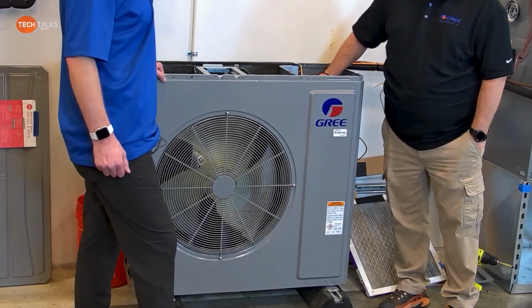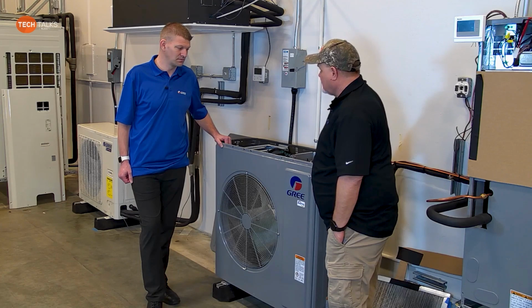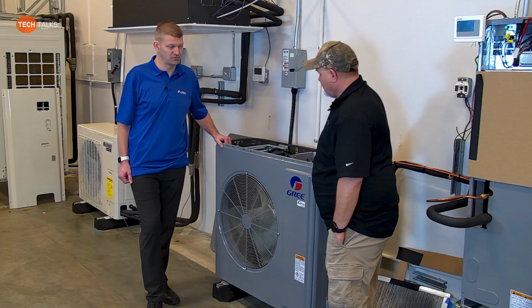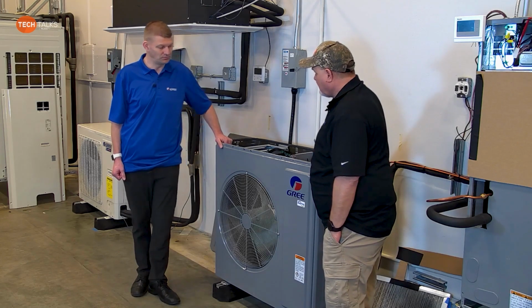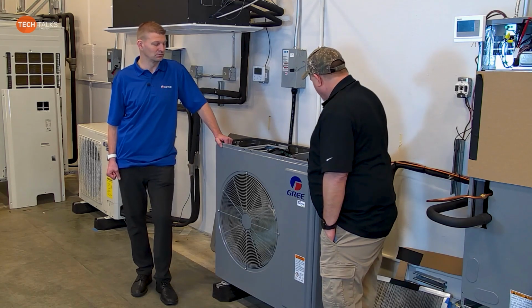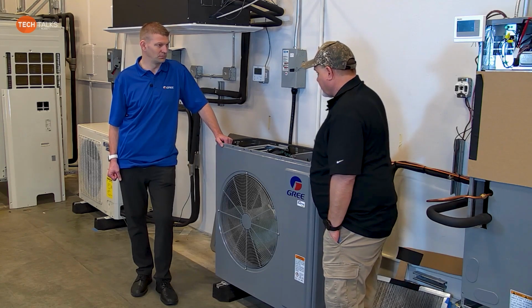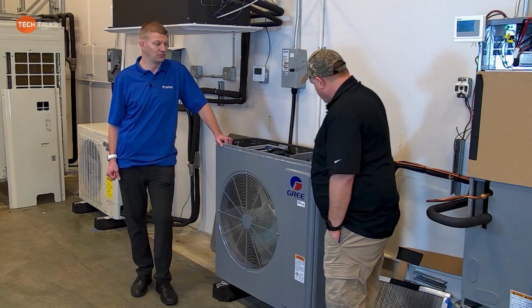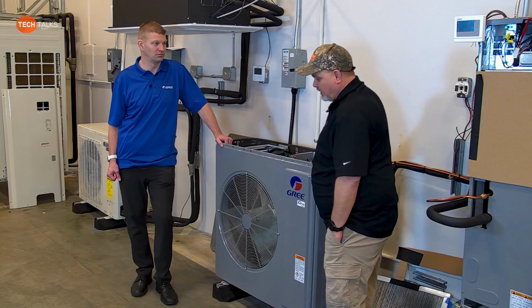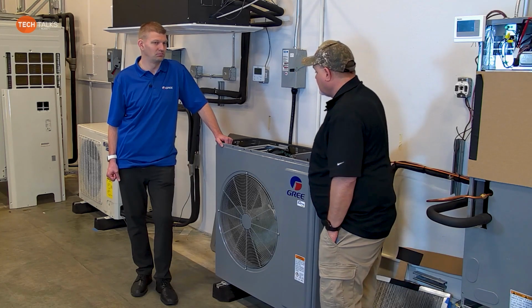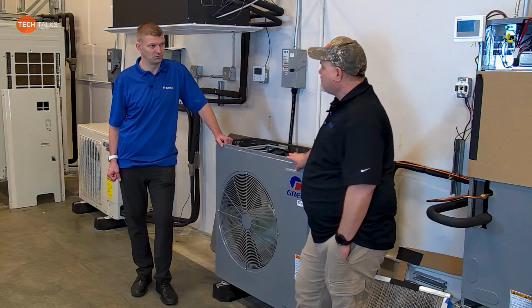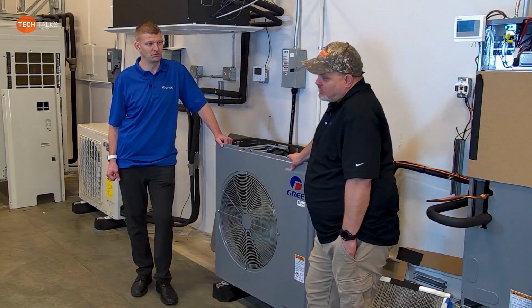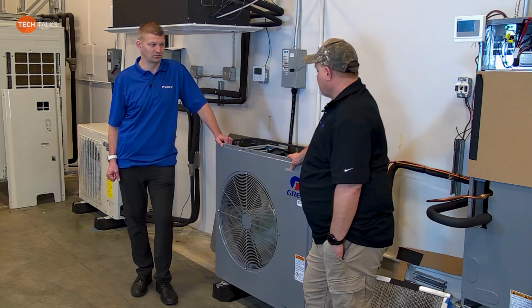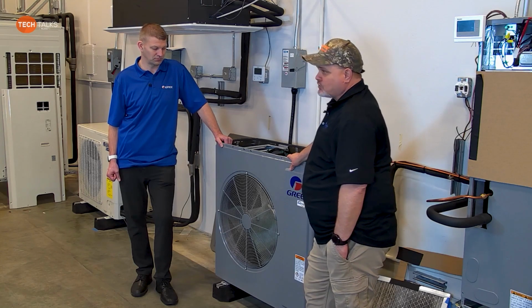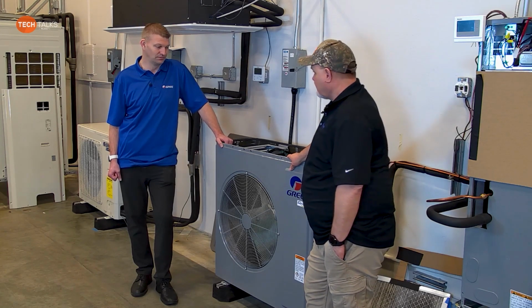From what I understand, they've relocated the fusible plug, and it's in a different piping of the circuit, so we should see fewer failures on the fusible plug. We didn't see a ton on the 410A model, but we did see some. And supposedly they went to a different supplier with the fusible plug. So we should be seeing fewer failures with the fusible plug on the R32 equipment as well. Just another FYI. So GREE does listen to us. Those are things that were brought up to them in previous conversations, and they do try to fix it.